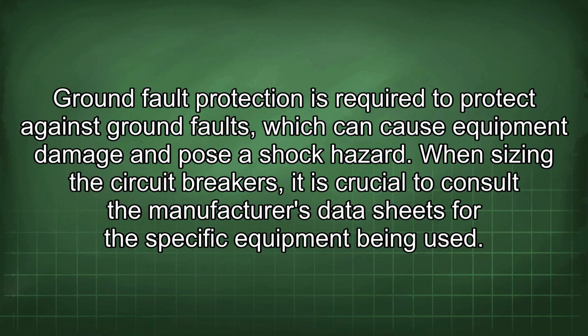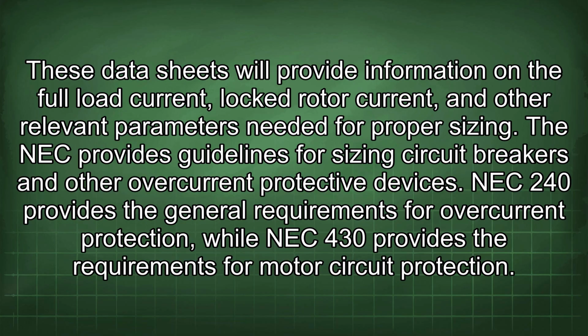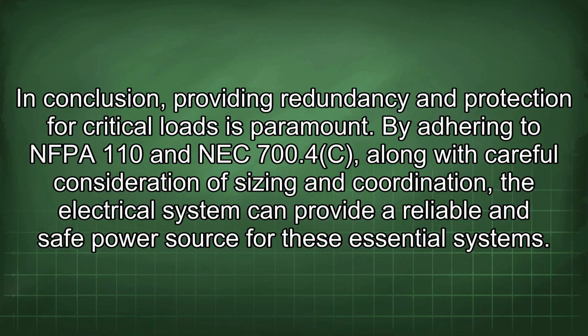When sizing the circuit breakers, it is crucial to consult the manufacturer's datasheets for the specific equipment being used. These datasheets will provide information on the full load current, locked rotor current, and other relevant parameters needed for proper sizing. The NEC provides guidelines for sizing circuit breakers and other overcurrent protective devices. NEC 240 provides the general requirements for overcurrent protection, while NEC 430 provides the requirements for motor circuit protection. In conclusion, providing redundancy and protection for critical loads is paramount. By adhering to NFPA 110 and NEC 700.4c, along with careful consideration of sizing and coordination, the electrical system can provide a reliable and safe power source for these essential systems.